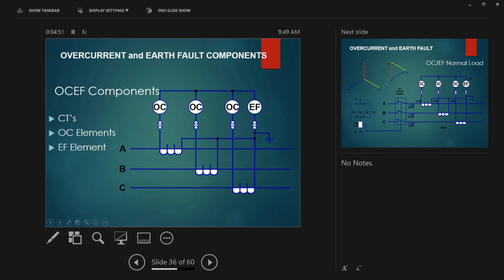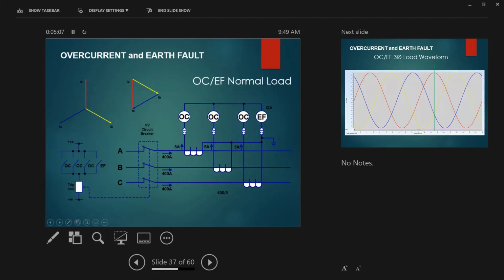This is your overcurrent, red, white, blue, or ABC, and any stray current will be picked up by your earth fault coil. You have to look at this as your protection relay terminals. This is your CT link, earth, and everything. On the 3-phase system, we normally have 120 electrical degrees apart from A, B, C. For star and delta it is the same. And if you maintain that angle, you will have no current flowing here. For example, you have balanced red, white, blue, 5 amps, 5 amps, all will be looped in this area because you have maintained the 3-phase angle over there.